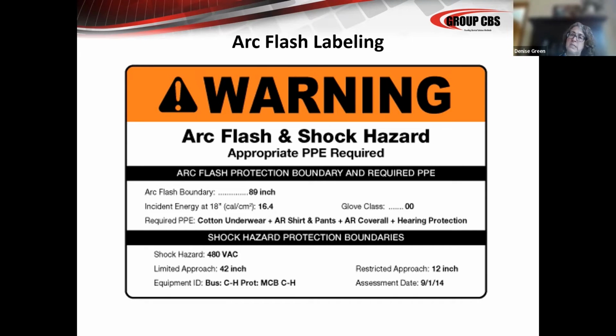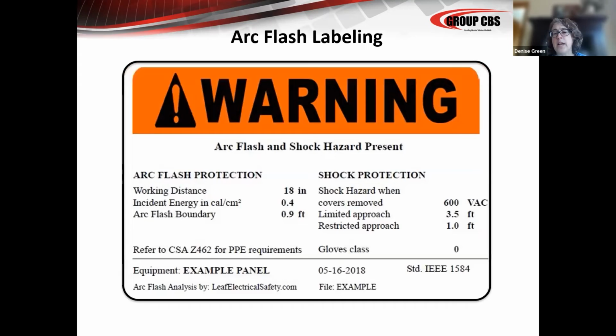So that's really important. This is a standard arc flash hazard label. This one was generated in 2014. I have another label to show you that was generated in 2018, and we're going to talk about concerns about labels and how to read them when we get to the 1584 section. This label was generated in 2018, and this particular label will have taken into account the newer version of the 1584 formulas, calculations, and components for calculation. So having your staff pay attention to the date that the label was created is also really important in determining their hazard when they're standing in front of it, along with the maintenance concerns.